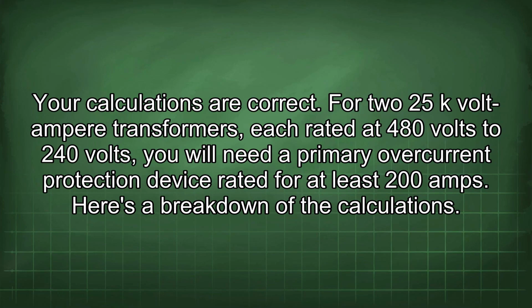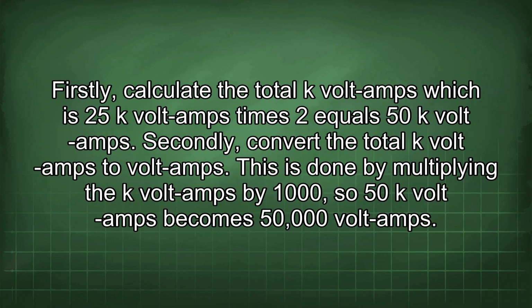Your calculations are correct. For two 25 kVA transformers, each rated at 480 volts to 240 volts, you will need a primary overcurrent protection device rated for at least 200 amps. Here's a breakdown of the calculations. Firstly, calculate the total kVA, which is 25 kVA times 2 equals 50 kVA.